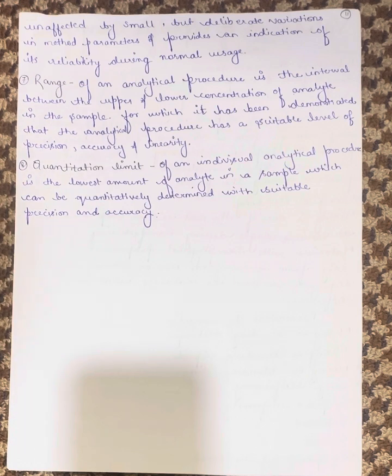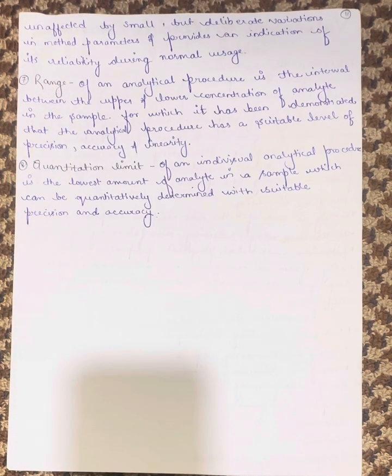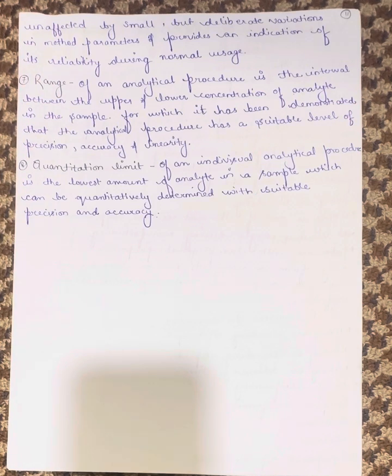Range of an analytical procedure is the interval between the upper and lower concentration of analyte in the sample for which it has been demonstrated that the analytical procedure has a suitable level of precision, accuracy, and linearity. Next, the quantitation limit of an individual analytical procedure is the lowest amount of analyte in the sample which can be quantitatively determined with suitable precision and accuracy.